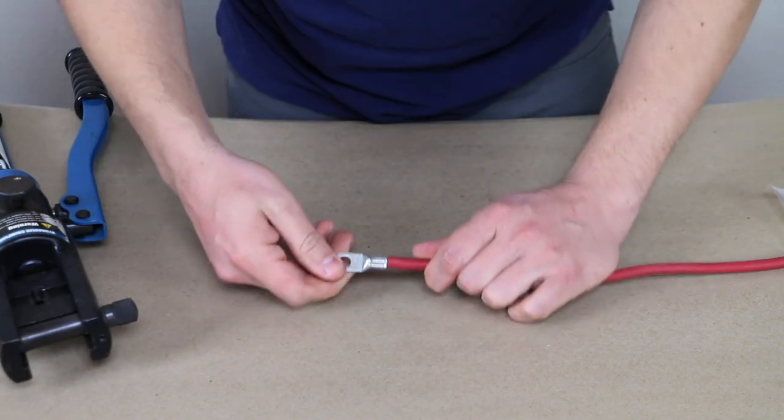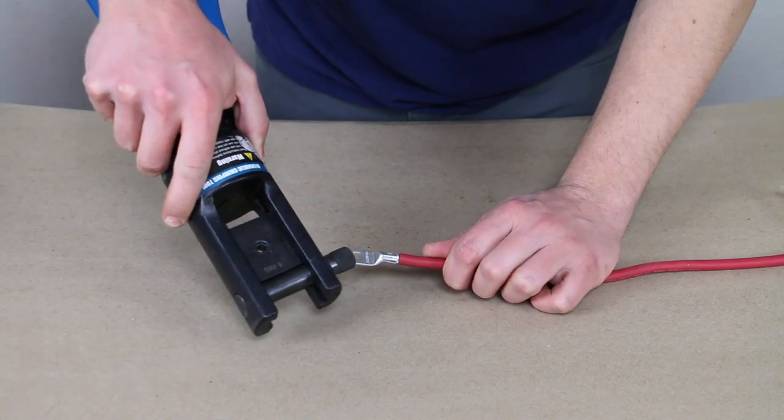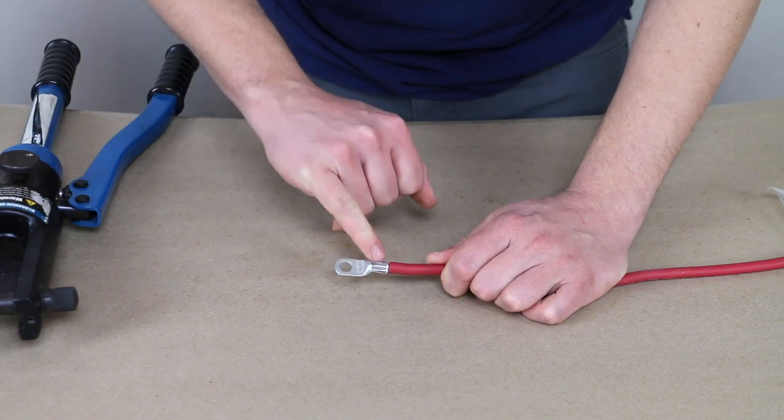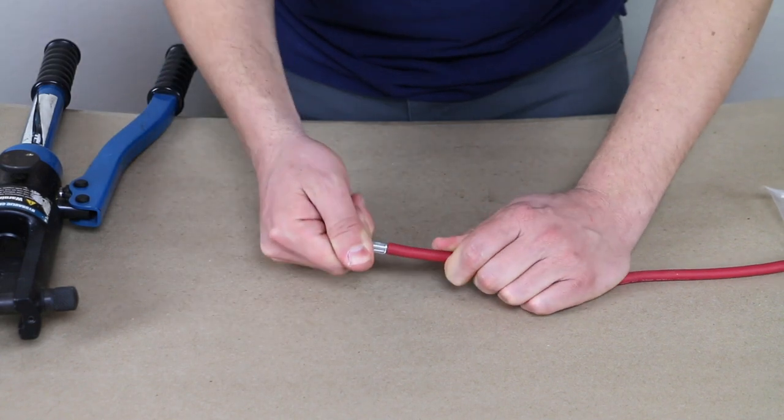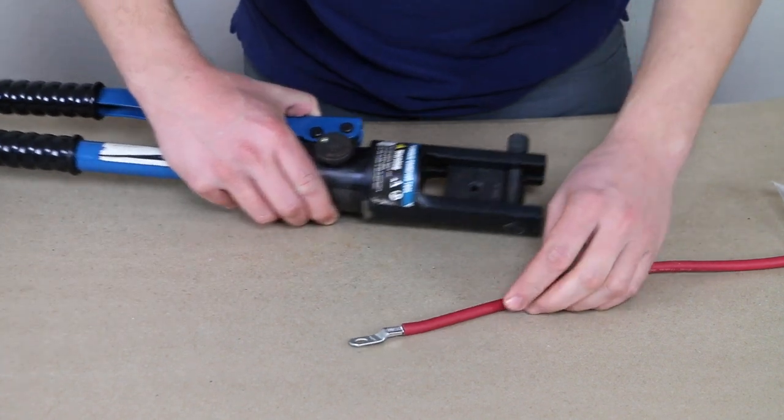So, pretty good crimp there. This is the actual six-gauge dies. So I didn't have to change sizes. We've got an excellent crimp. The metal didn't squish out too much. Overall, a great crimp. And the Temco definitely delivers.